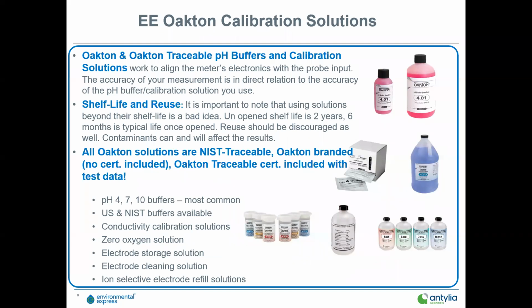So last, let's talk about calibration solutions. We offer a couple of types of pH buffers. The Oakton branded is our NIST traceable branded buffer. It does not include a NIST cert. The Oakton traceable branded buffer does include that NIST certification. So again, if you're having to provide an audit trail for a regulator or auditor, this is key. You'll want to go with the NIST traceable or Oakton traceable product. The cert comes with it, and the auditors and regulators will accept that usually without question.